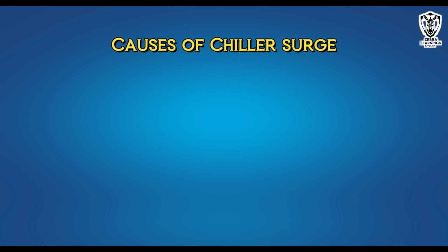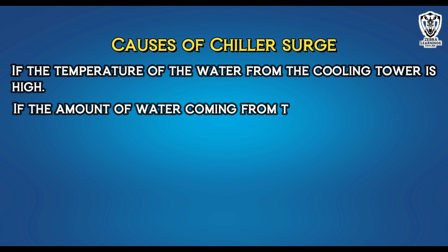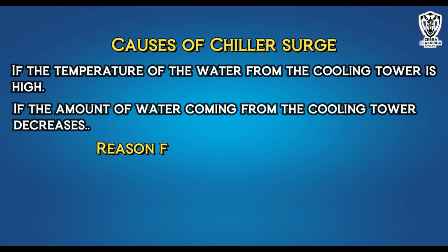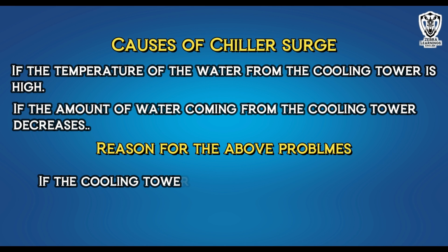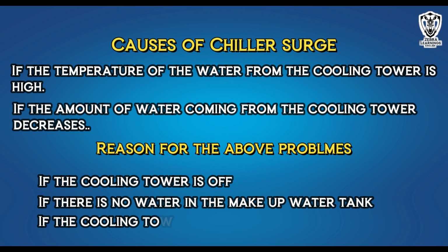This problem can occur if the temperature of the water coming from the cooling tower is high or the water level is low. The reasons for the above problems are: if the cooling tower is off, if there is no water in the makeup tank, or if the cooling tower belt is cut, the water temperature may increase and the water level may decrease. So, this problem can be avoided by maintaining the cooling tower properly.